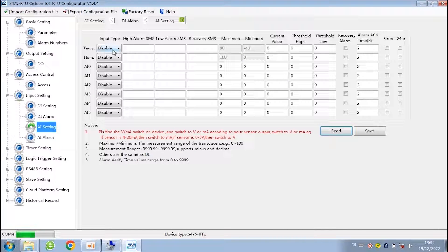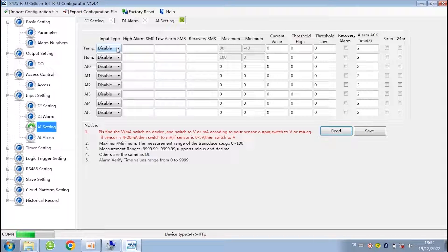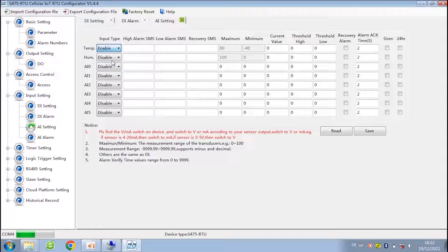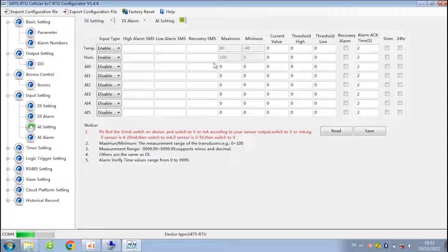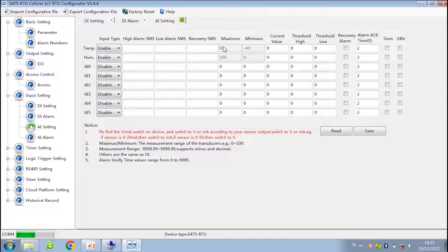There are two parts of analog input setting. First is temperature and humidity. RTU can connect to AM2301 sensors to read temperature and humidity value. You need to set threshold value, SMS content, and the alarm act time. The act time means only when the value changed more than this time, it will be treated as a true alarm.